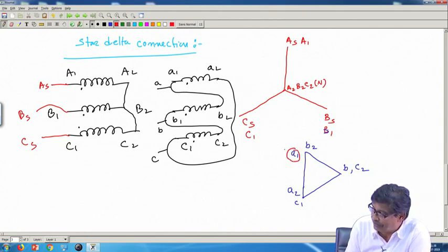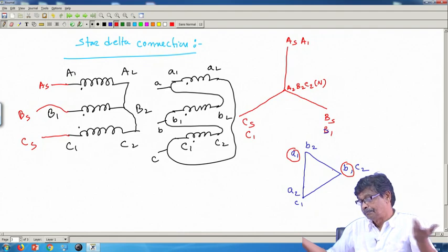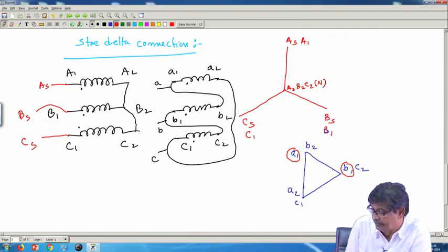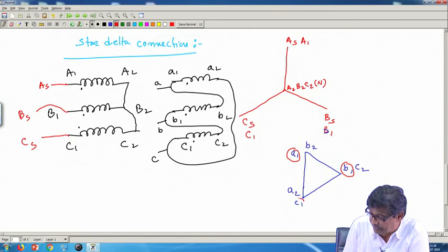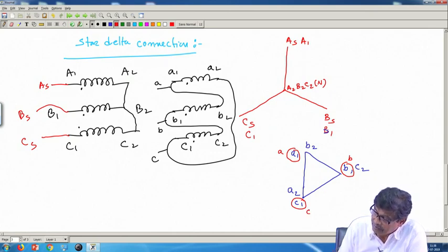And then I am telling, mark this, please follow the instructions carefully, so that you will never make a mistake while working with a 3-phase transformer in the laboratory or at the site. So, A1 B1 C1, these are the things, this is A, this is my B, this is C. So, balanced 3-phase voltage will be obtained. So, here is the artificial neutral, because in delta connection there is no neutral. So, the A phase voltage with respect to this neutral, and the A phase voltage of the primary is this vertical line, therefore, it is 30 degrees.